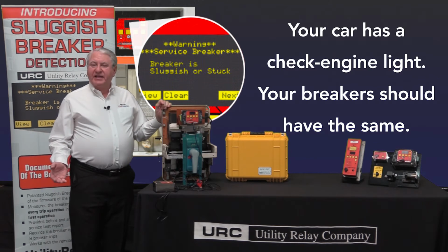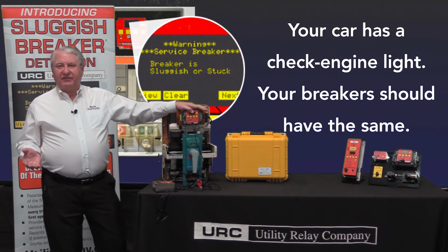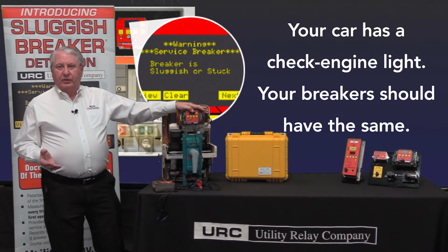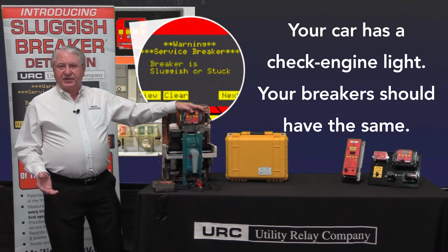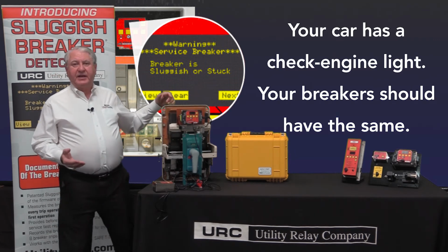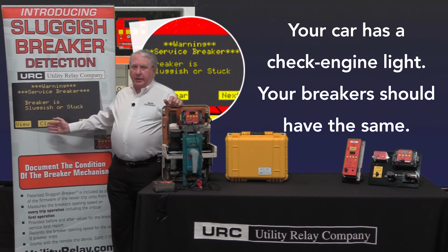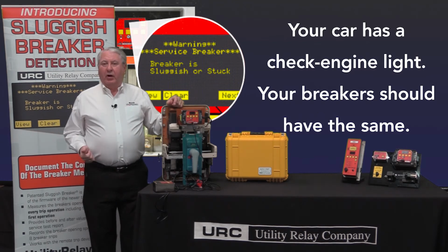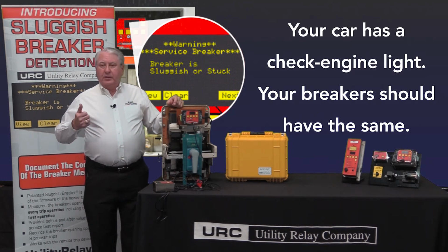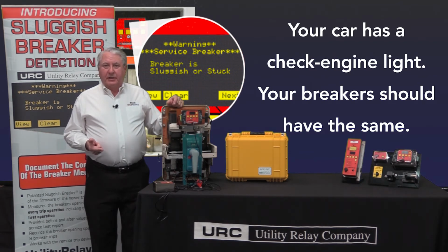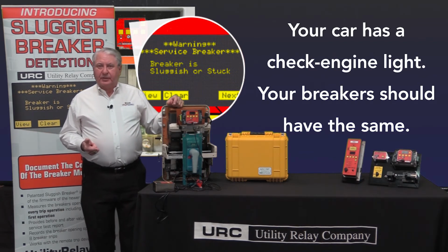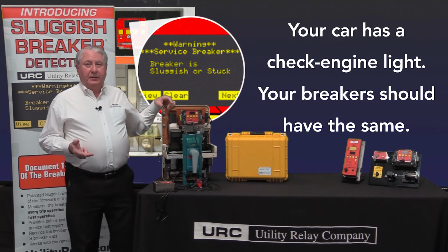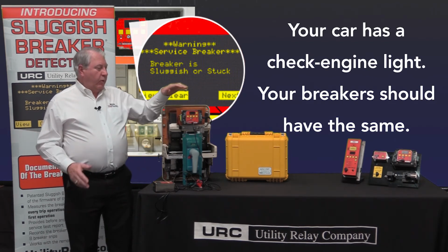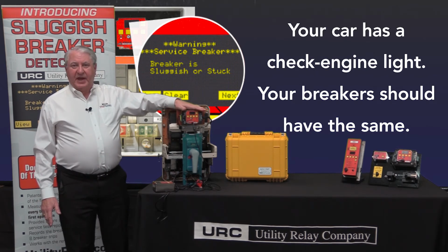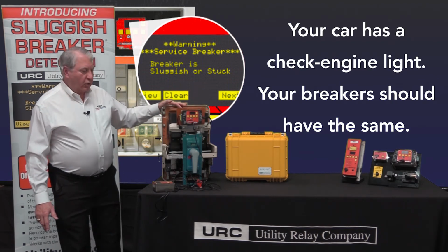So why is this important? Well, it's a safety issue. It's a safety issue for your equipment. It's a safety issue for your personnel. If a breaker is getting into a point where it's slow or sluggish, you can get into higher arc flash incidents. You can be exceeding your coordination numbers as far as your equipment is concerned, and you can really cause a risk to personnel and equipment. So we think it's important to know from a maintenance standpoint and from a service standpoint whether your breaker is getting into a slow or sluggish condition.